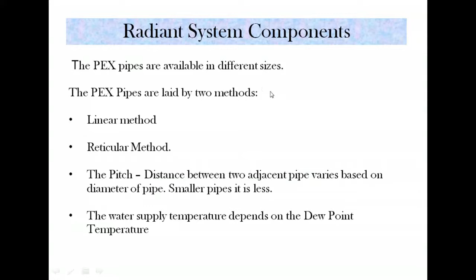When you use 9 mm pipe, the pitch is something like 50 mm. That is, the distance between the two pipes is 50 mm. If you have a 16 mm pipe, the pitch, that is the distance between the two pipes, is 100 mm. But when you have a 20 mm pipe, the distance between the two pipes is 150 mm. Then there are methods of doing it: linear method, reticular method. As I said, I explained what the pitch is, that is the distance between two adjacent pipes.